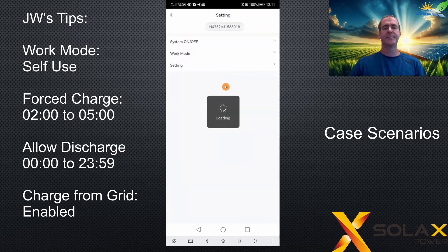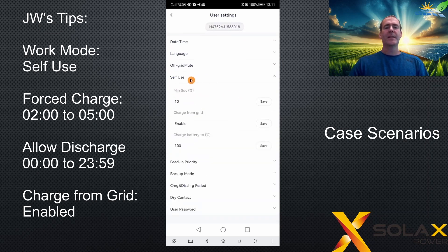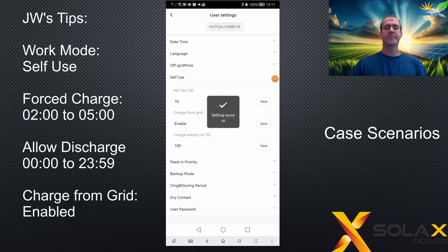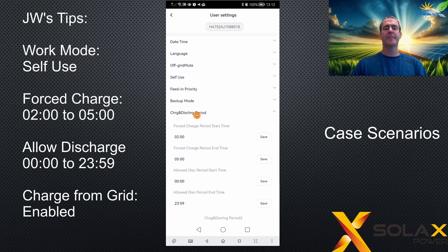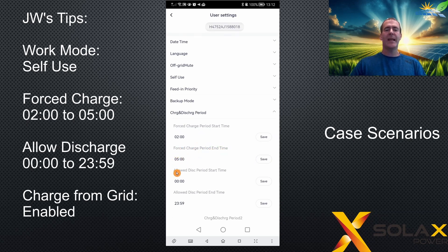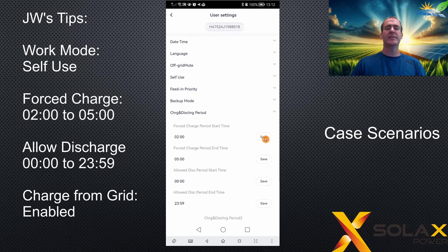Click into the basic settings and type the zero-zero-zero-zero user settings code. Click on the self-use category and make sure that charge from grid is set to enable, then click save. Moving down to the discharge period, set the force charge start time to 2 o'clock and the end time to 5 o'clock. The allowed discharge period still needs to be from midnight to 23:59, which means the battery will be used to power the house loads at all times. Make sure you click save against each item — the charge times and discharge times can overlap, and the charge period will take precedence before reverting to the discharge period.